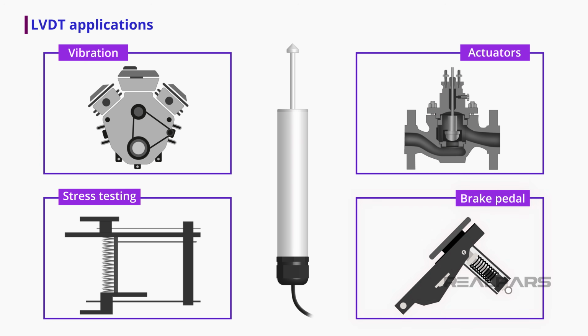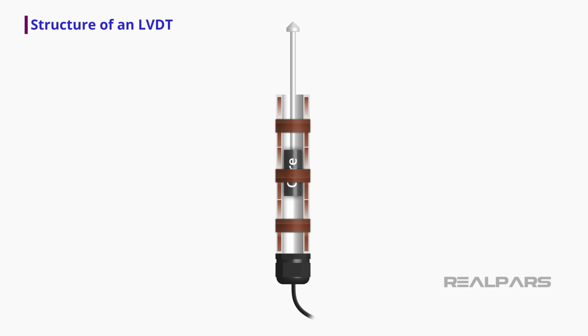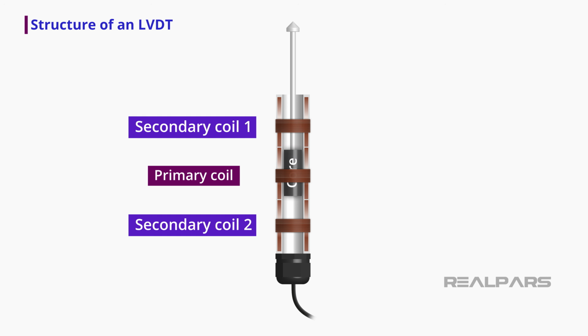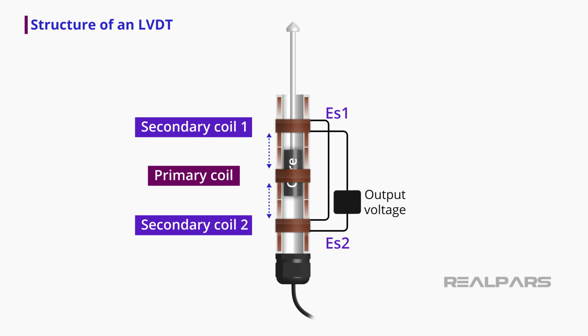Looking at a cutaway of an LVDT, we can see that the LVDT consists of three high-density glass-filled coils wound around a hollow insulated tube that is non-magnetic. The primary coil is located in the center, and the other two are identical secondary windings located at an equal distance from the primary coil. The differential part of this sensor's name comes from the fact that those two secondary coils are in opposite phases. They are electrically 180 degrees out of phase with each other and are connected in series. This connection results in an output that is the difference between the voltages in these two windings.